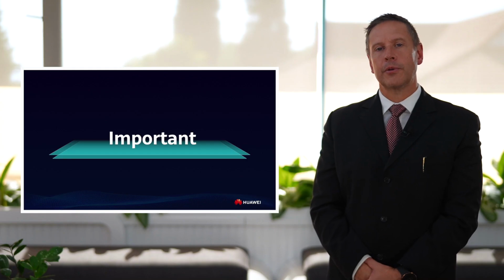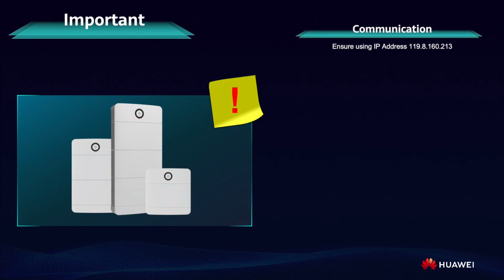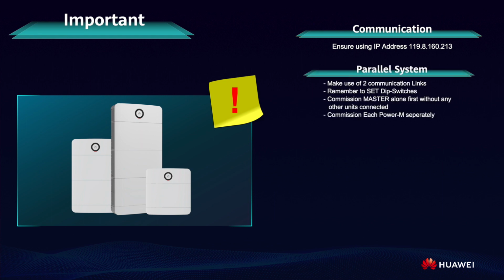Important steps on the procedure of commissioning the Power M. For the communication, ensure that the IP address used is 119.8.160.213. In parallel systems, make sure that you make use of 2 communication links. Remember to set the dip switches. Commission the master alone first, without any other units connected. Commission each Power M separately.